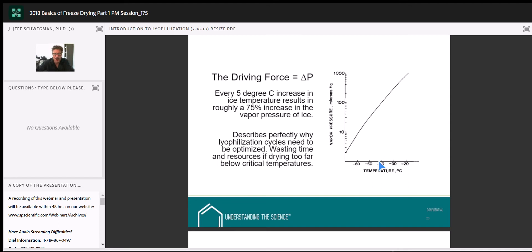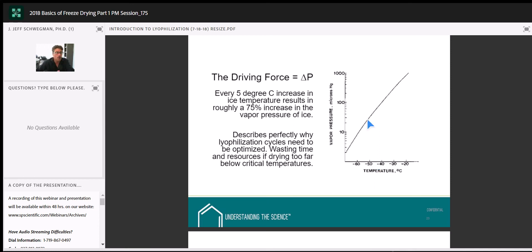Some steps of freeze-drying: product freezing, thermal treatment or annealing if needed, then once everything's frozen we kick on our vacuum pump — technically we're then in primary drying. The goal of primary drying is to remove the frozen ice. Secondary drying begins when all frozen ice is gone, and this is where we remove unfrozen water loosely associated with the dried matrix. We conduct secondary drying until we reach our target moisture, then backfill with inert gas or air, seal the product, or in bulk drying, move it to a controlled humidity environment.